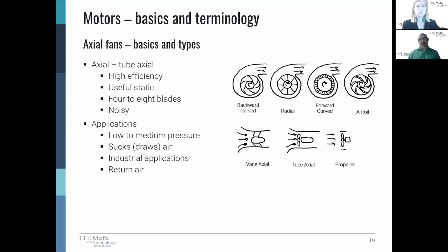Now, if I want another example of an axial fan, I could go to tube axial. Now, these are a lot more common. A tube axial fan kind of produces airflow the same way an airplane wing produces aerodynamic lift. Now, one of the key characteristics is that air is actually swirling as it leaves. So we might need something to straighten that flow out if we think we're going to change directions too terribly quick.